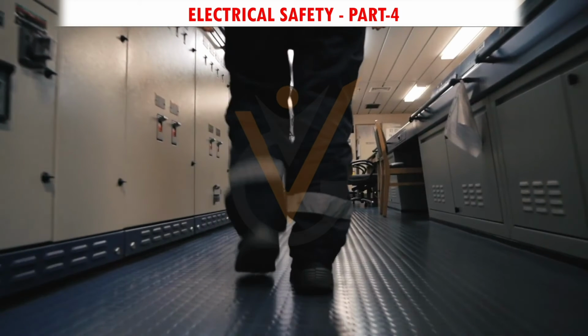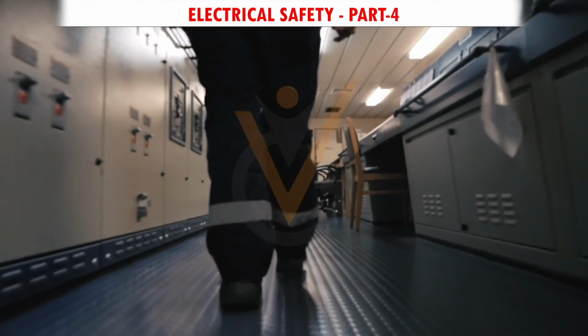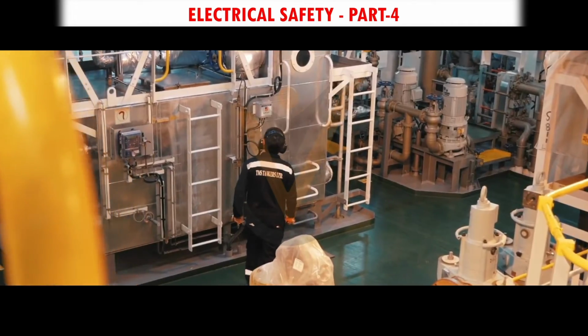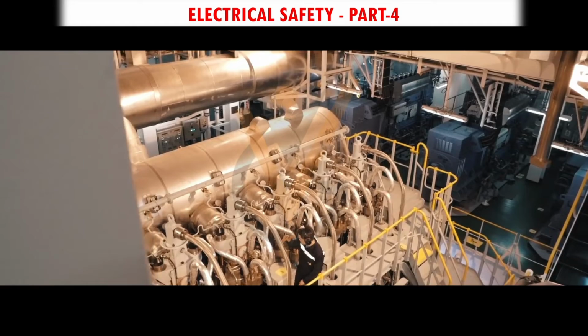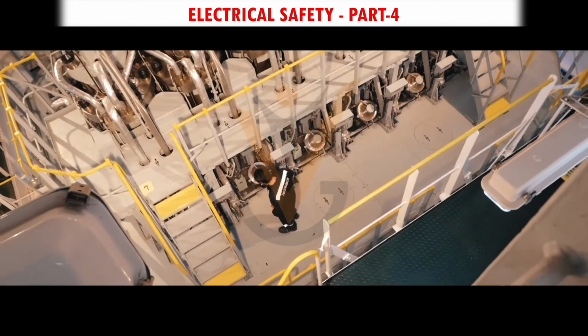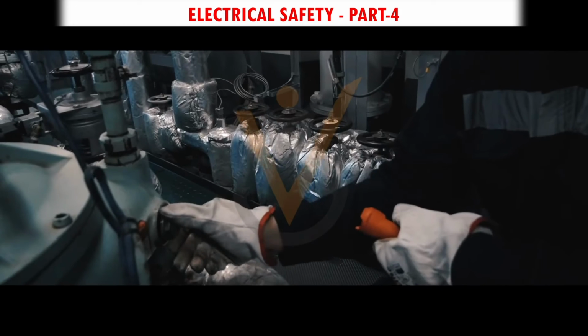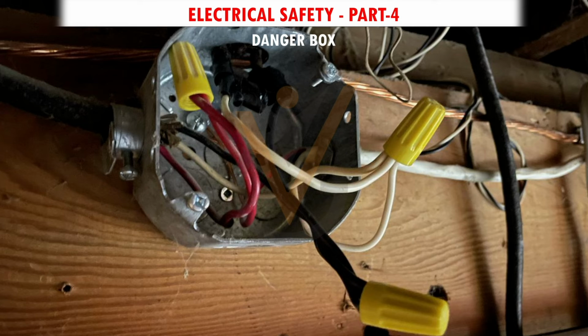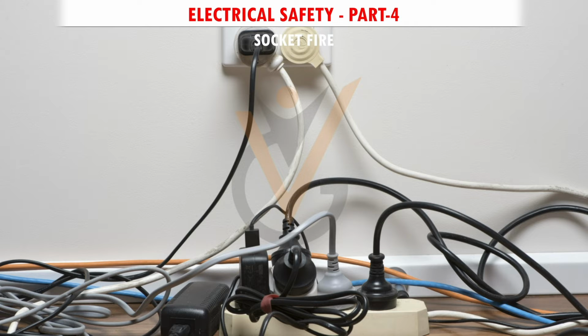Steps to minimize the risk of an electrical shock and fire on board ships. Start with the first round of the day. Check all electrical motors, wiring, and switches for abnormal sounds, variation in temperatures, and loose connections. Ensure that all electrical connections are inside the panel box so that no one can touch them accidentally. In the accommodation area, multiple socket plugs shouldn't be used.